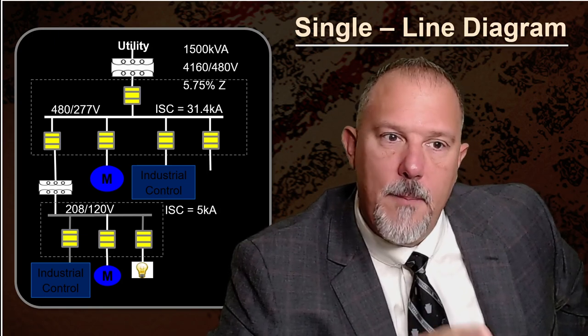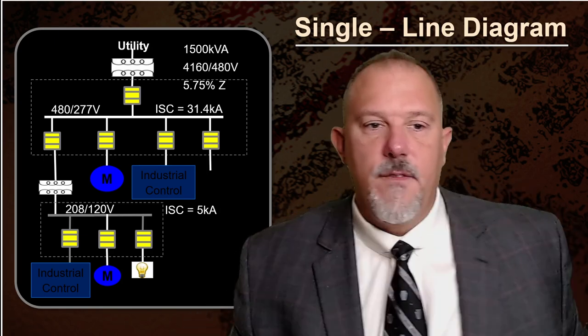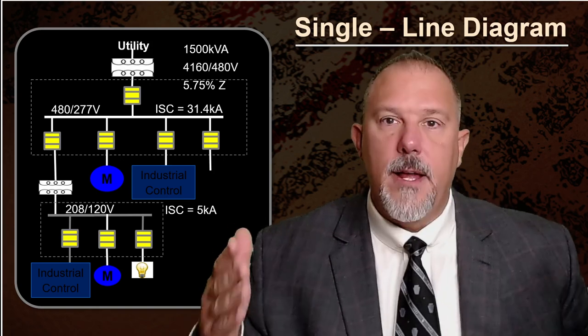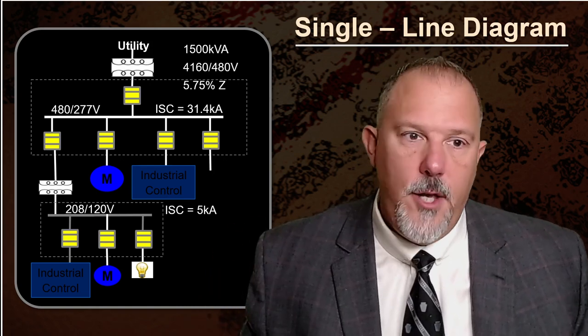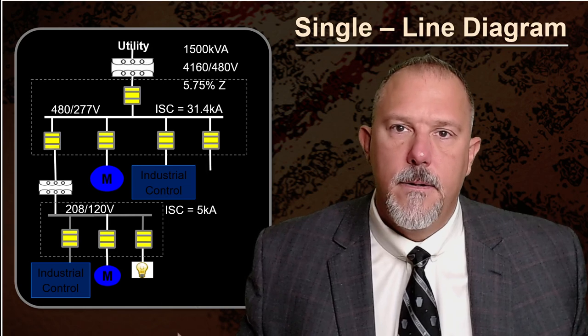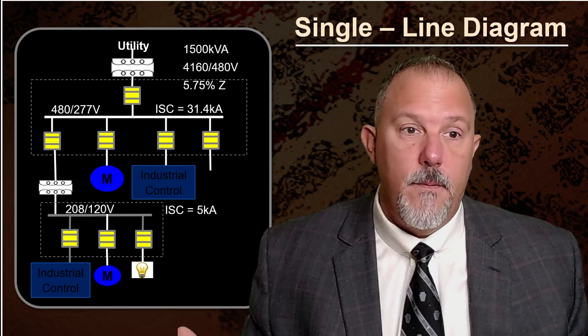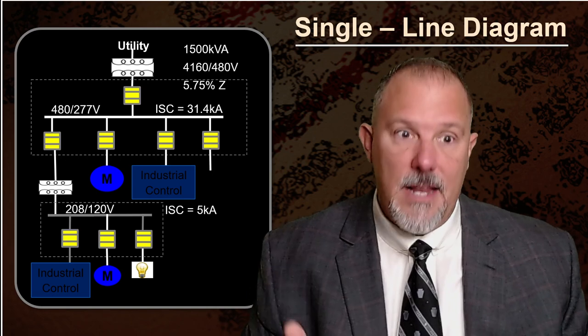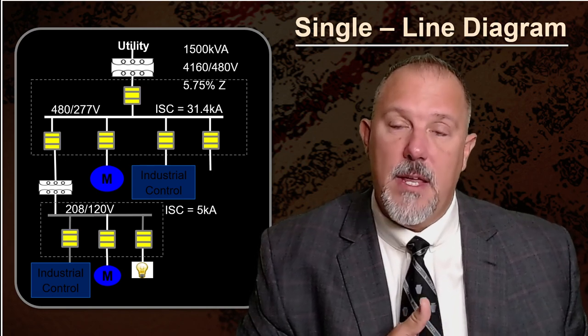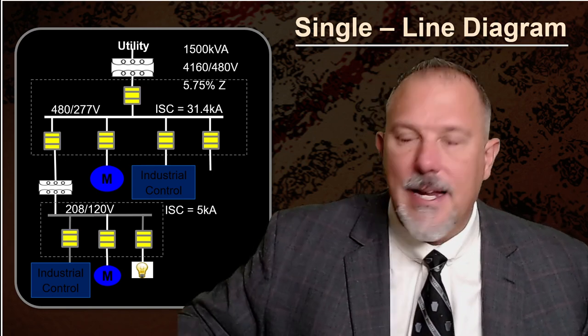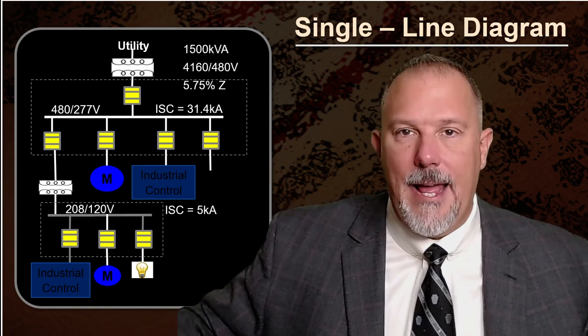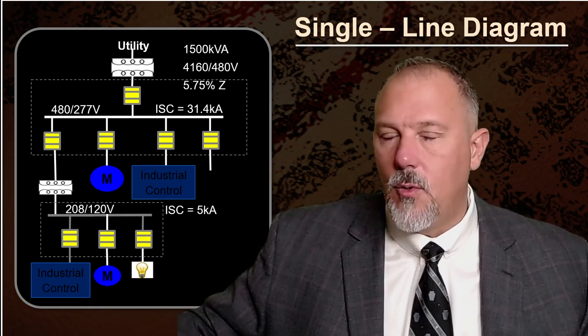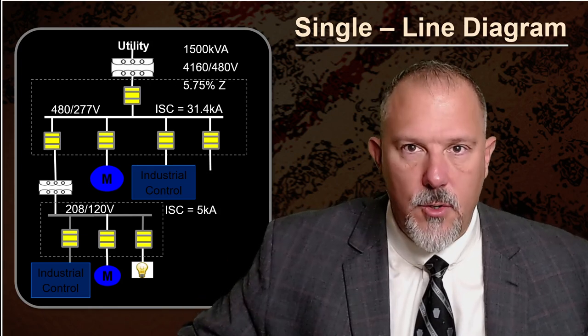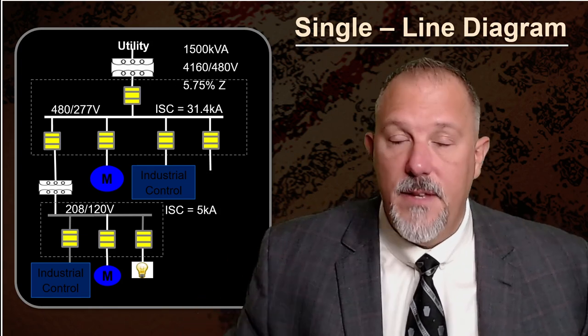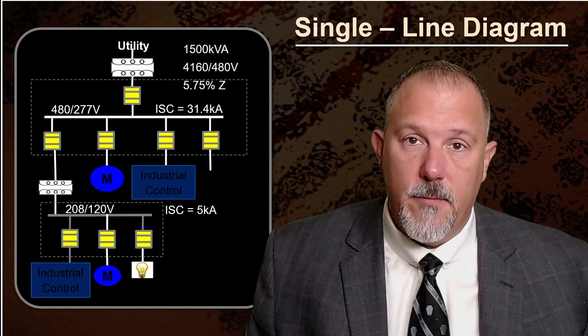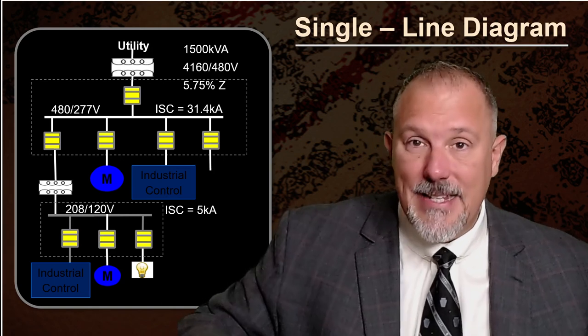Why do I pick a large one? If the full load amps of that transformer is 100 amps, do I pick a 100 amp breaker or put in a 100 amp fuse? No. Why wouldn't I? Because I want that fuse or breaker to let the transformer energize. What am I thinking about? Inrush currents. Anytime I'm putting in an intentional delay, whether it be for selective coordination, motor start, motor inrush currents, in this case, transformer inrush currents, I'm adding an intentional delay.